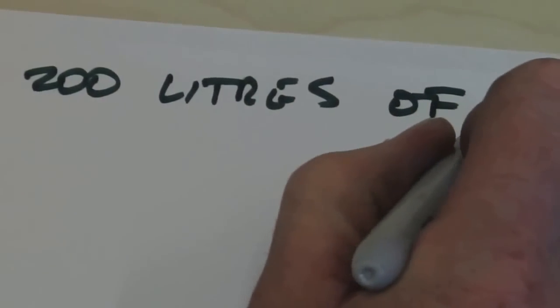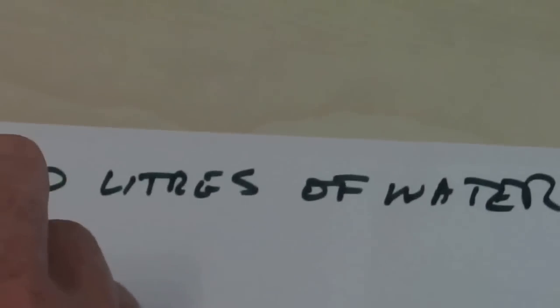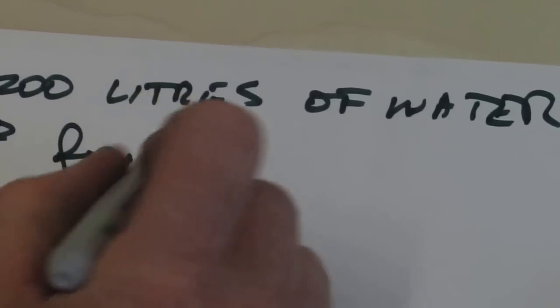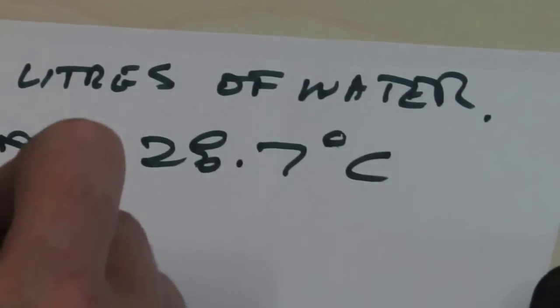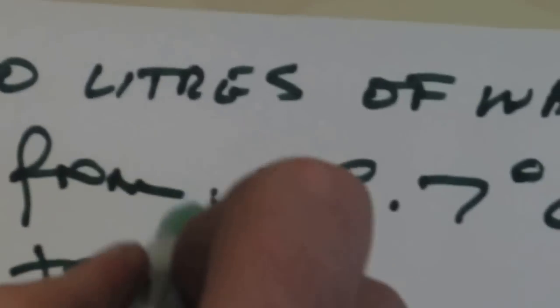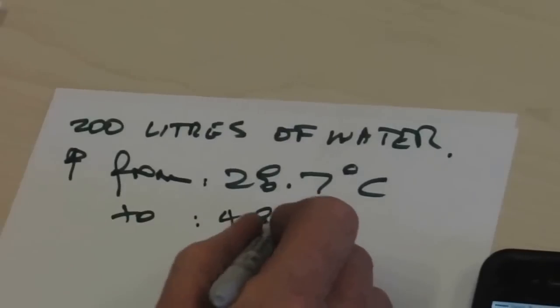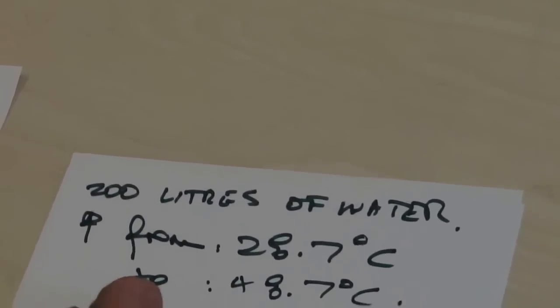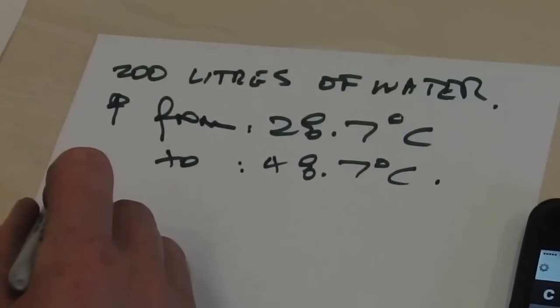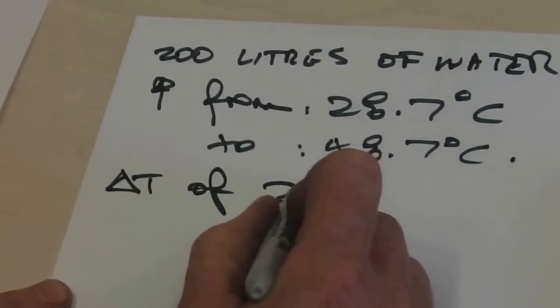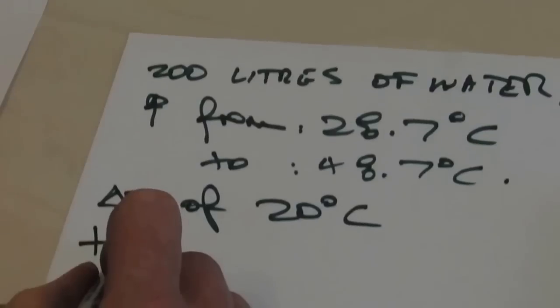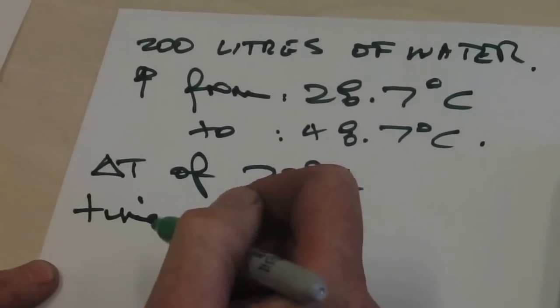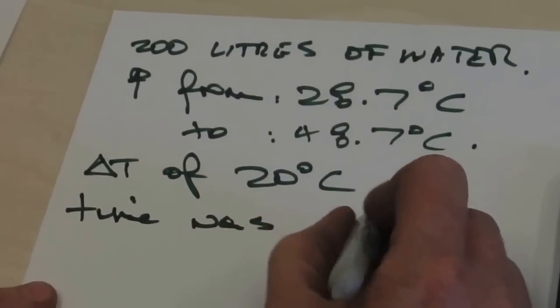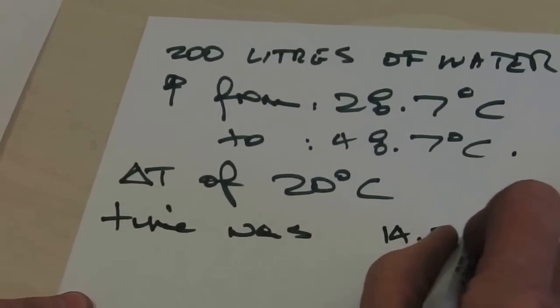To summarise, what we just did before was we had 200 litres of water, and we lifted the temperature of the water from 28.7 degrees C to 48.7 degrees C. So that's a temperature difference, or a delta T, of 20 degrees C, and the time taken was 14 minutes 33 seconds. Thanks, Pete. Was about 14.5 minutes.